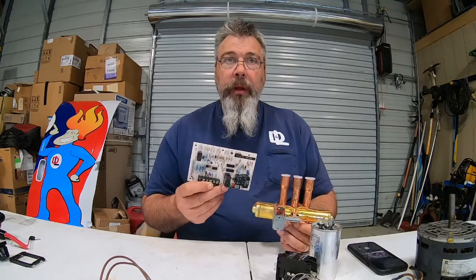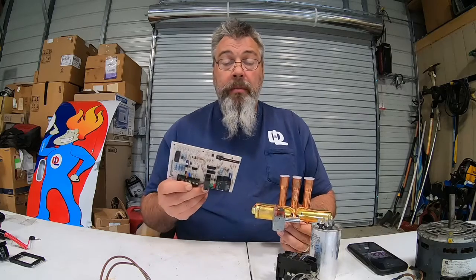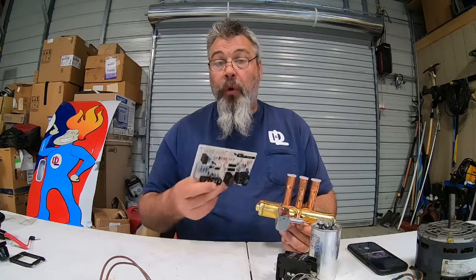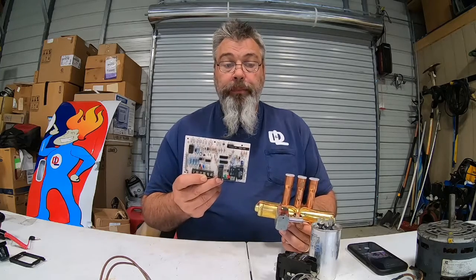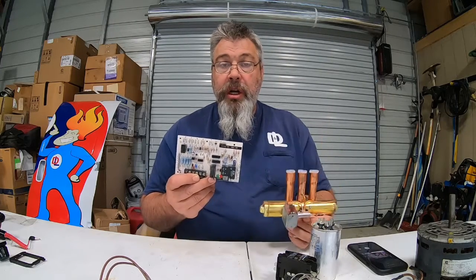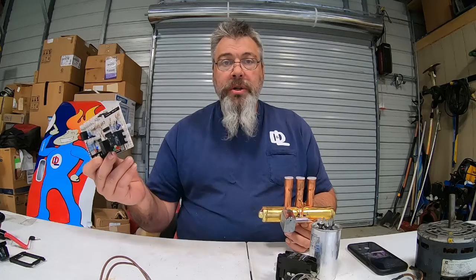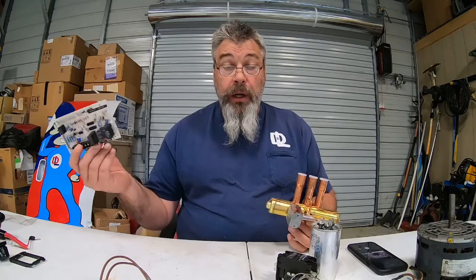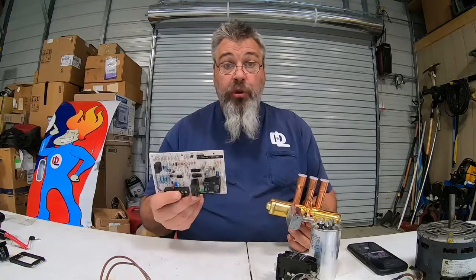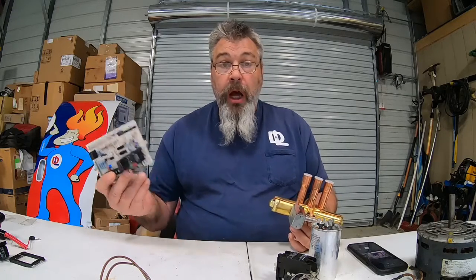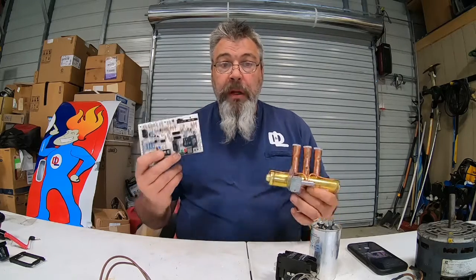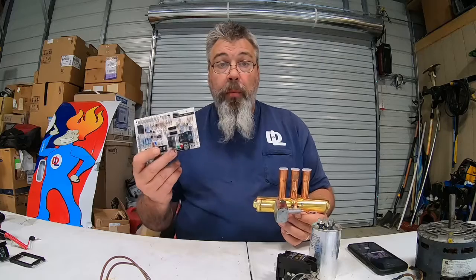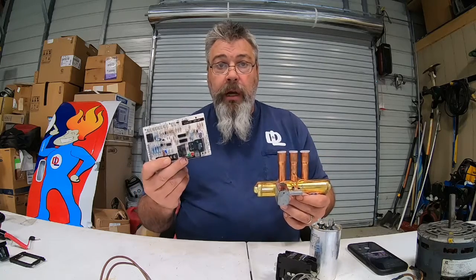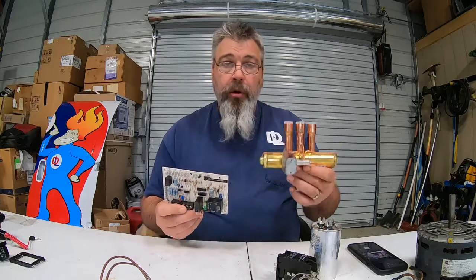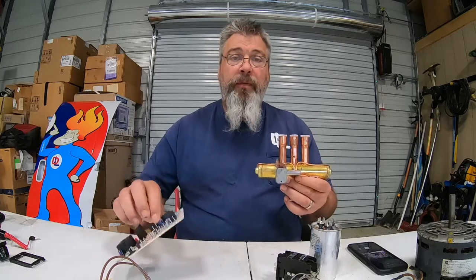Some of us have gas backup, some of us have oil backup, what we call fossil fuel or dual fuel systems, where once your heat pump is no longer efficient, it drops out and brings on your secondary or supplemental heat. Could be either or: oil, gas, electric. Some people have hydronic systems that come off the water heater and feed hot coils. So that's what happens in there. You get your control board that says, hey, you need to do this when I tell you to do it, and your reversing valve, which reverses the flow of refrigerant.